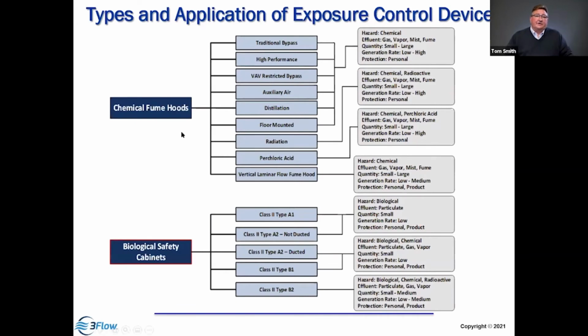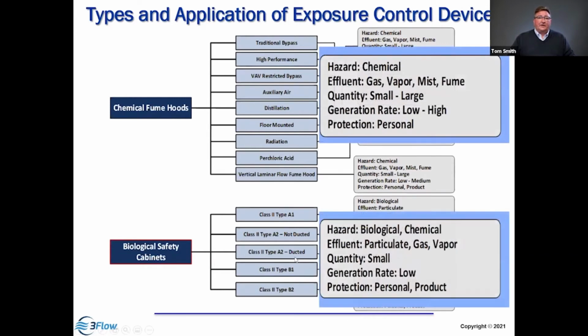And so this CIFA document helps to define the different types of hoods. There's many different types of chemical fume hoods, from benchtop bypass hoods to floor-mounted hoods. These different types of hoods may have different applications, and they're not to be confused with a biosafety cabinet, which is more about use of biological materials. By looking at this document, it helps to define the hazards, the type of quantities, and the generation rates, and what the hood is for, so that you can better define the type of hood and what our expectations are for proper operation.